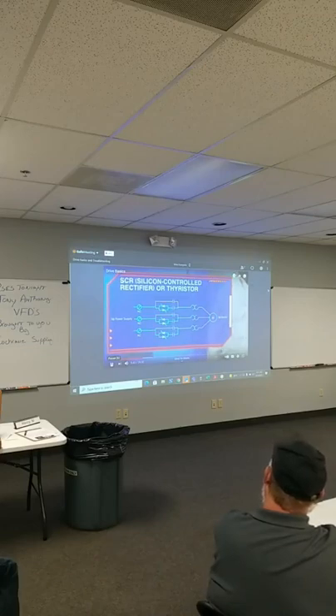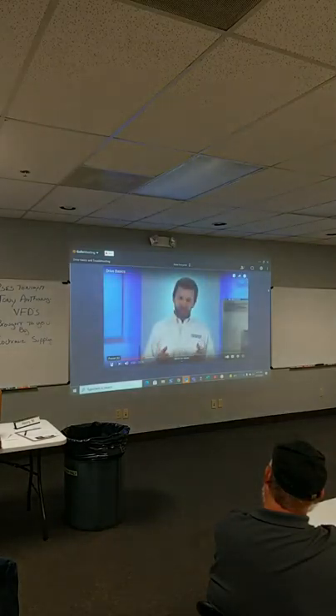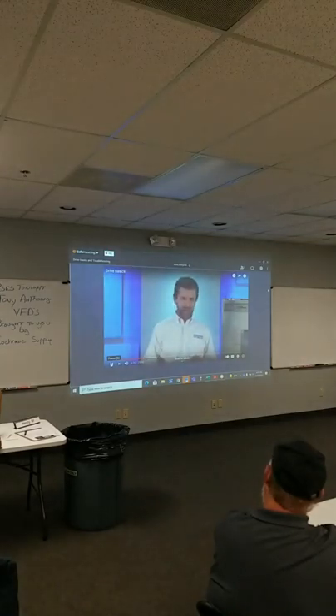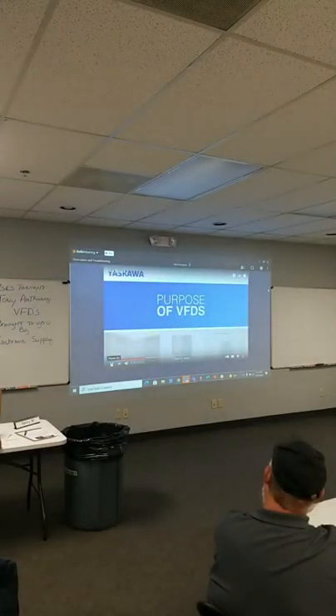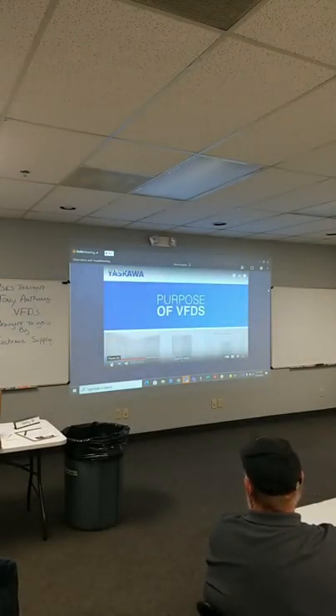SCR, or thyristor control. The solid state device is controlled to pass only a portion of the voltage waveform to the motor. These offer a smooth start to the given system and limit the current draw by the motor. When the motor is up to full speed, the unit then bypasses the soft start function and full voltage is applied. These units have limited start allowances for a given time period, but offer smooth starts instead of the stepped previous methods. So that brings us to the purpose of variable frequency drives.